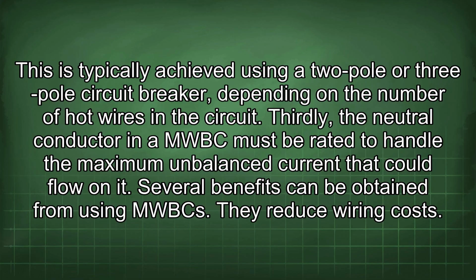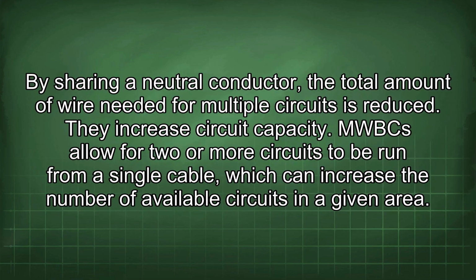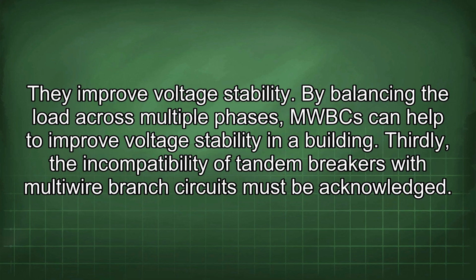Thirdly, the neutral conductor in an MWBC must be rated to handle the maximum unbalanced current that could flow on it. Several benefits can be obtained from using MWBCs. They reduce wiring costs. By sharing a neutral conductor, the total amount of wire needed for multiple circuits is reduced. They increase circuit capacity. MWBCs allow for 2 or more circuits to be run from a single cable, which can increase the number of available circuits in the given area.